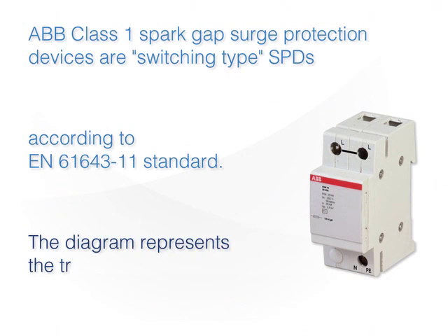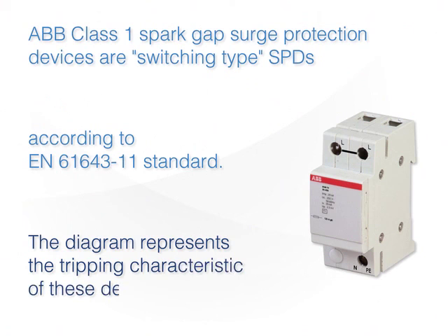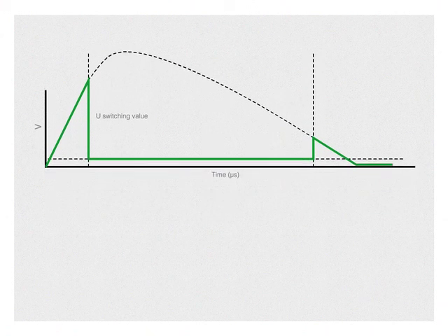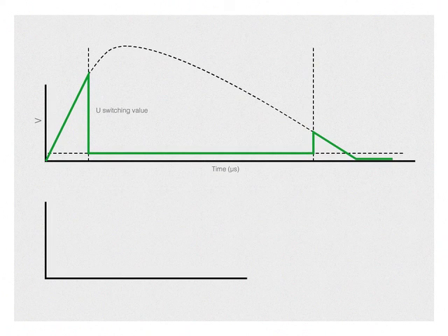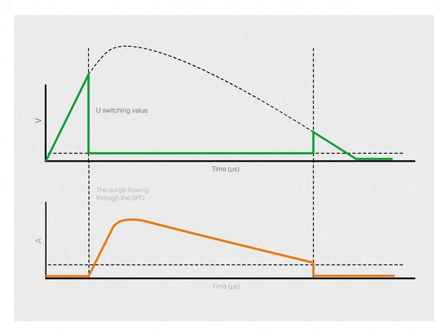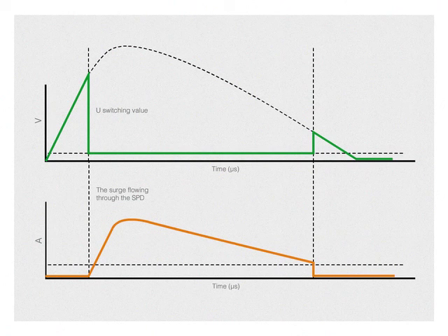The diagram represents the tripping characteristic of these devices. As seen from the figure, at the occurrence of a certain level of overvoltage — the switching value — the voltage across the module collapses suddenly to just a few volts, the value corresponding to the arc voltage. The more rapid the switching process, the more the maximum voltage level across the SPD is reduced, and the less the downstream electrical equipment is solicited.